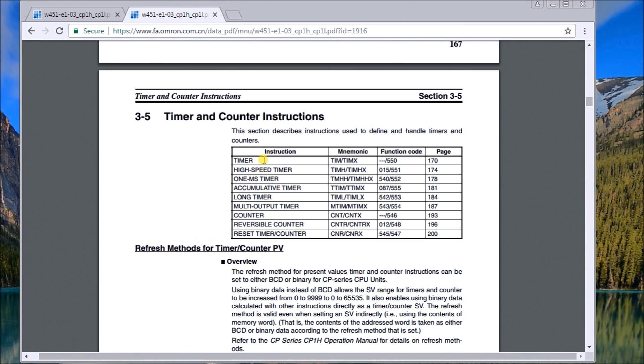In section 3-5 we have a series of basic timers: a regular timer, a high-speed timer, a one-millisecond timer, an accumulative timer, a long timer, and a multi-output timer. You'll notice on the right-hand side we have TIM and then TIMX. The difference is that the regular TIM uses BCD code for its set value, while the X represents binary code for the set value.